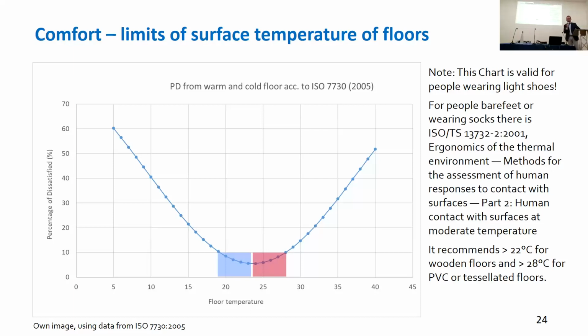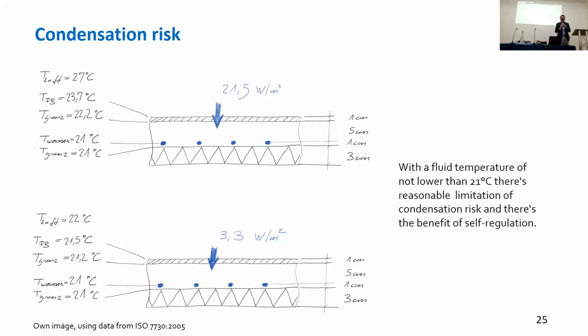I think in offices, floor cooling can be easily done, because then you're in the world of wearing shoes. But in the residential area, it's okay unless you get lower temperatures than this. Having said this, there's another but. In the floor, the condensation risk has to be taken very seriously. The condensation risk has to be taken always seriously. And what I'm talking about, cooling surfaces, is only valid for areas with an absolute humidity in the range of 15, 16 and 17 gram per kilogram of dry air. So never play around with radiative cooling in the tropics.